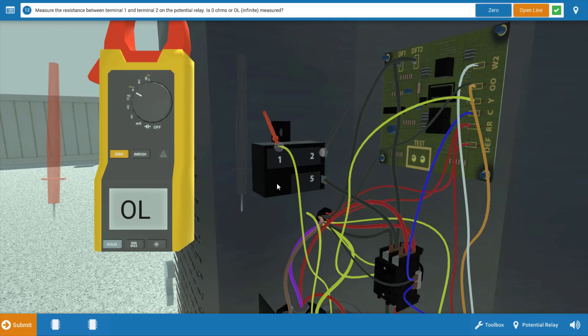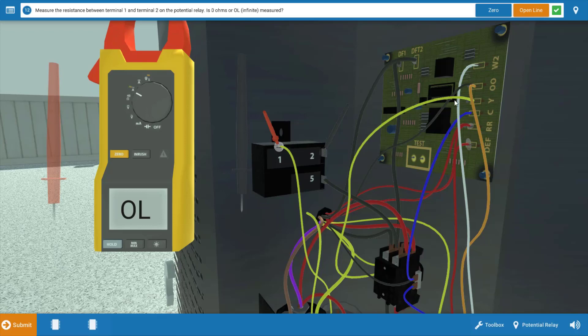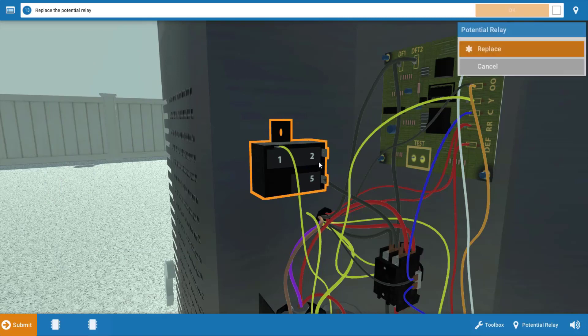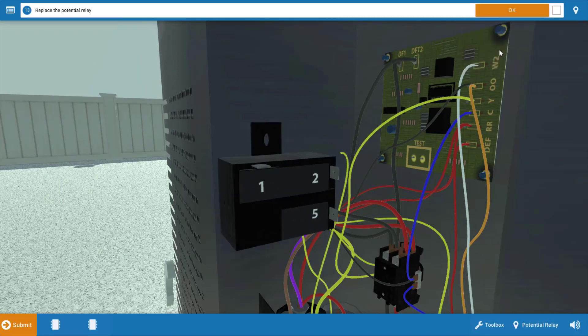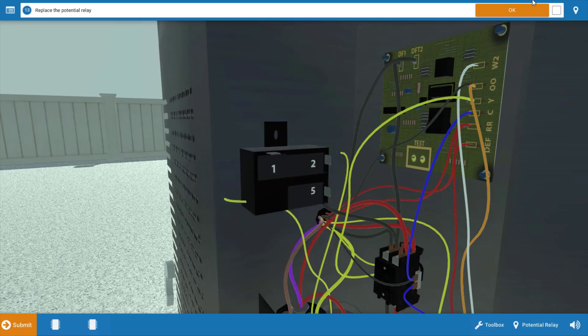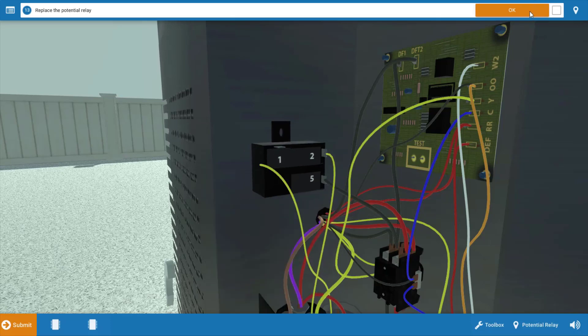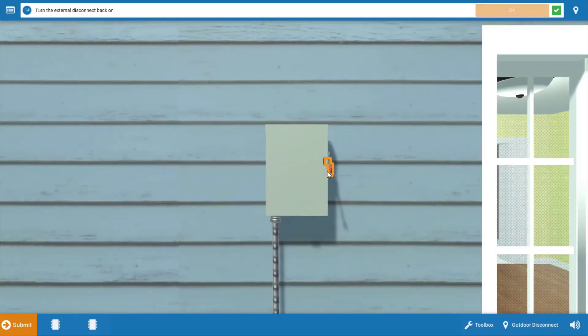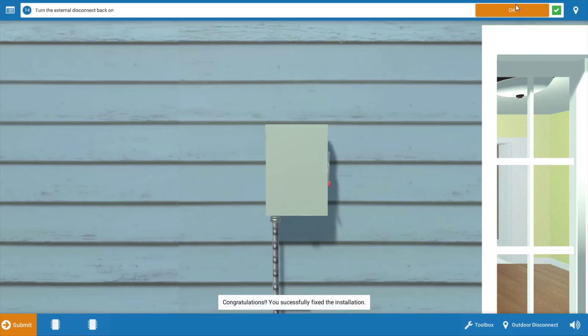This indicates those contacts are open and they're faulty. And this means that the potential relay is at fault. And we're going to need to replace it. So after clicking open or infinite on the procedure guide, simply click on the potential relay and replace it. And once you've replaced it, we're going to need to turn the power back on and watch one full cycle of operation to make sure everything works properly.